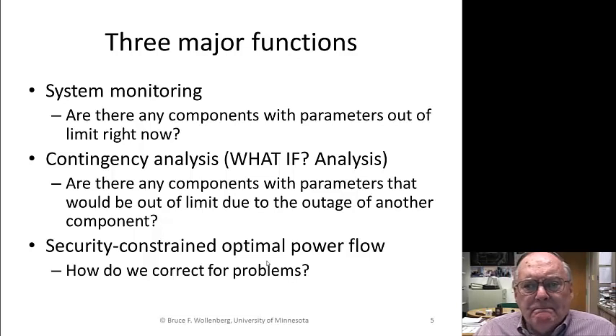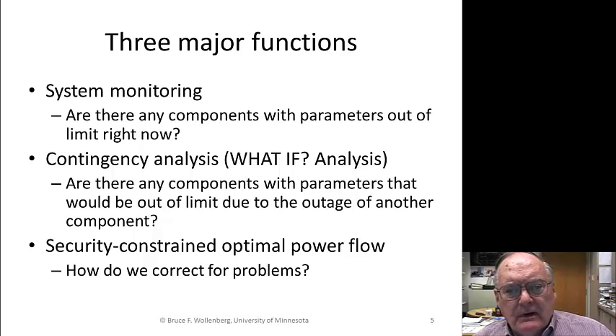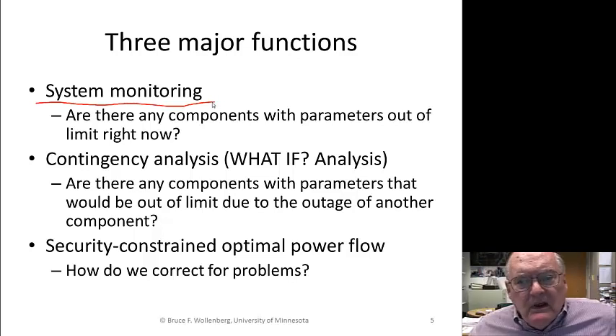to try to make sure that your system is secure, we have three major functions. First is system monitoring. The idea here is that we'd like to know, are there any components with parameters out of limit? And what we're going to do is we're going to sample data from measurements. We're going to run all those measurements past limit checking in our SCADA system, and we're going to run state estimation to get very accurate values of all of those quantities and test those flows and voltage magnitudes against limit values that are stored in the computer.